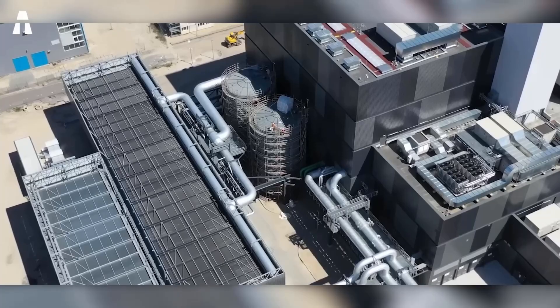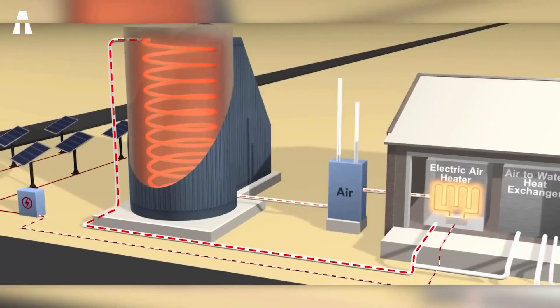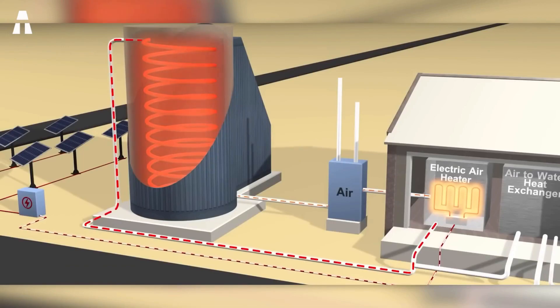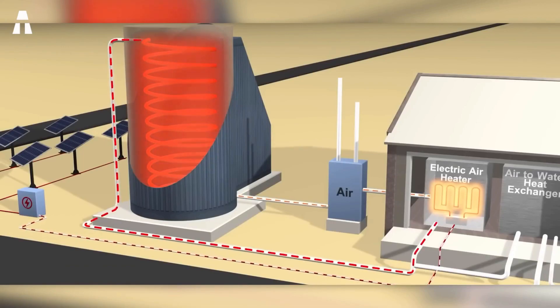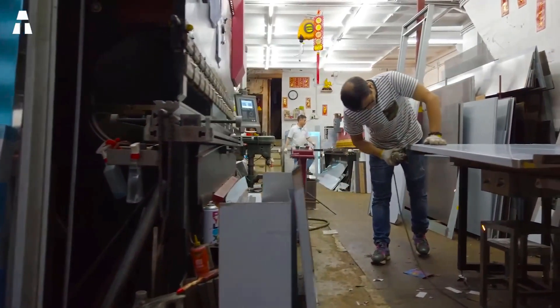While it may sound complicated, the heat production is actually based on resistive heating — this is how common appliances like toasters work. Their tank is well insulated from the outside environment, minimizing heat loss over time, reaching temperatures of up to 600 degrees Celsius. So their base unit can retain heat for months. To recover this energy, simply circulate fresh air through the hot sand pipes. The end result is hot air that can produce cleaner steam for industrial processing, heating public water, or heating homes.